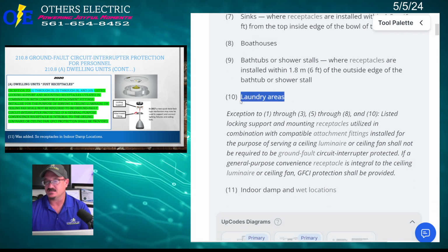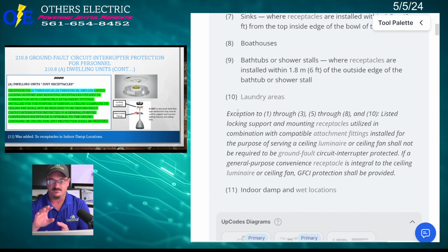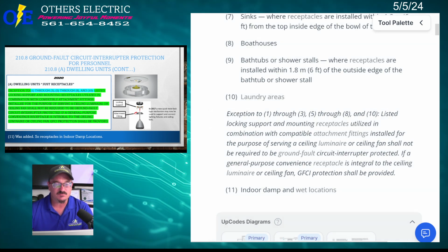And 10, laundry areas. So in those areas that I just listed, this type of device is excluded from being GFI protected, okay? We're going to read that, okay? Listed locking support and mounting receptacles utilized in combination with compatible attachment fittings installed for the purpose of serving a ceiling luminaire or ceiling fan shall not be required to be ground fault circuit interrupter protected. If a general purpose convenience receptacle is integral to the ceiling luminaire or ceiling fan, GFCI protection shall be provided.